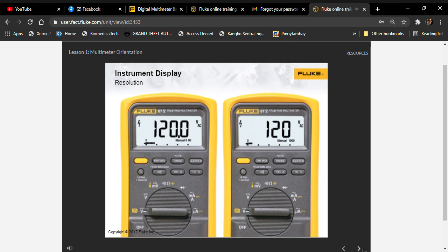Resolution is a measure of how fine a measurement is. A high resolution means that smaller changes can be displayed. For example, these two multimeters are measuring the same circuit. If the voltage changes by tenths of a volt, the one set to the higher resolution will display the change. The other one, set to the lower resolution, may not show the change because it can't display anything smaller than a volt. The rightmost digit shown on the display is the smallest displayable fraction of the measurement.